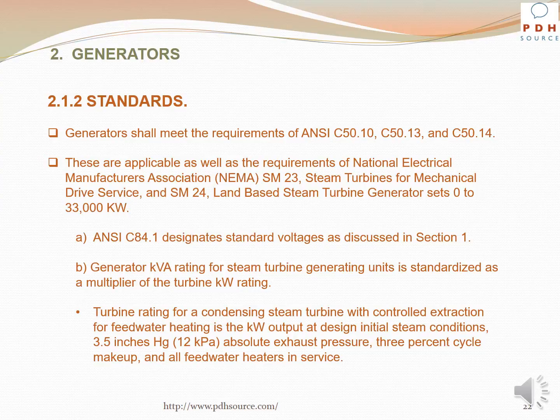Generators shall meet the requirements of ANSI C50.10, C50.13, and C50.14. These are applicable as well as the requirements of NEMA SM23, steam turbines for mechanical drive service, and SM24, land-based steam turbine generator sets 0 to 33,000 kilowatts. ANSI C84.1 designates standard voltages as discussed previously.